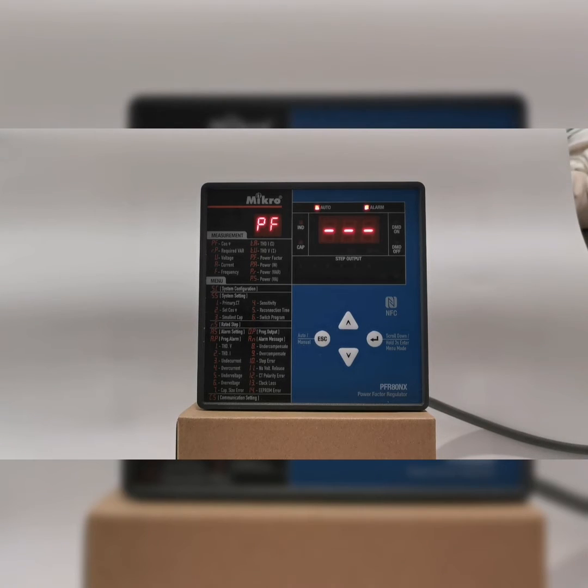This power factor regulator comes with a primary CT setting, so you need to set your CT ratio according to your primary CT. In order to set the primary CT, you can press the enter button.